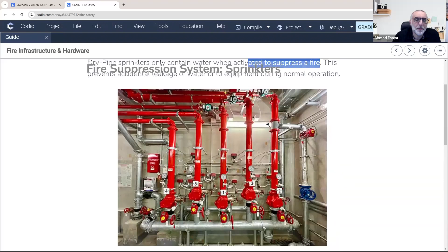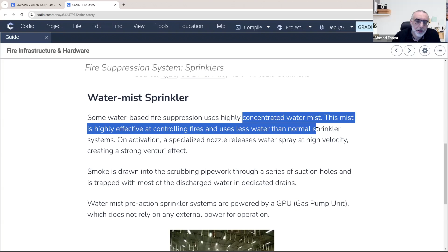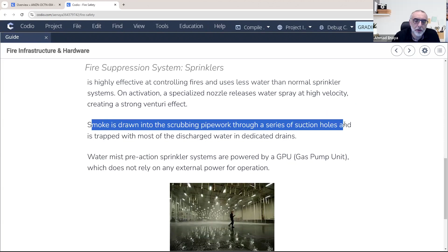Now there is an advanced way of sprinklers. Instead of using water, they use water mist, which is less damaging to the equipment. They just spray concentrated water mist. This mist is very effective in controlling the fire, uses less water than the sprinklers, and can control the fire faster. It has a system to also suck the smoke, and a system to take the extra water. So it is a whole system that can do all this.